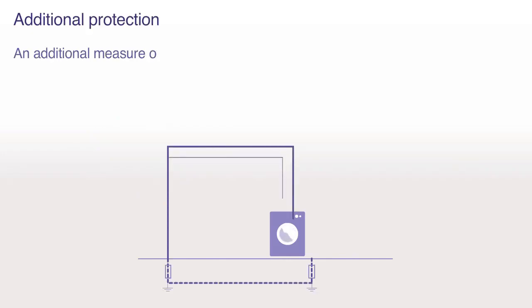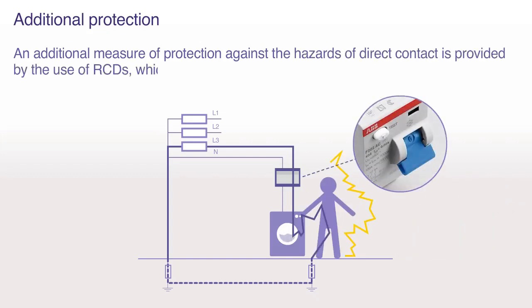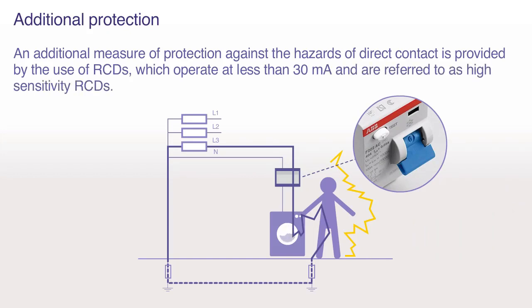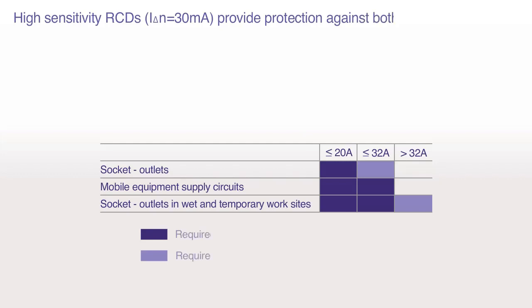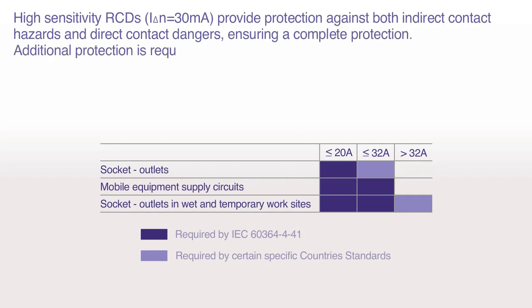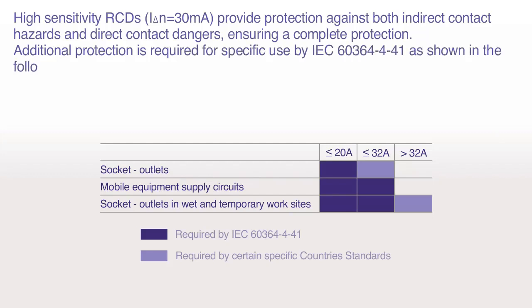Additional protection. An additional measure of protection against the hazards of direct contact is provided by the use of RCDs, which operate at less than 30 mA and are referred to as high-sensitivity RCDs. High-sensitivity RCDs, sensitivity equal to 30 mA, provide protection against both indirect contact hazards and direct contact dangers, ensuring complete protection. Additional protection is required for specific use by IEC 60364-4-41, as shown in the following table.